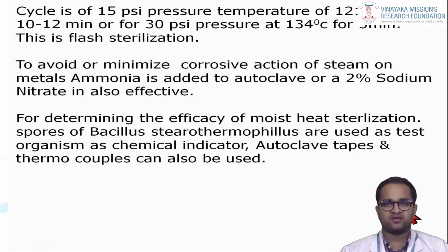Okay? The cycle is 15 psi or pounds pressure at a temperature of 121 degrees Celsius for 10 to 12 minutes or 30 pounds pressure at 134 degrees Celsius for 3 minutes.